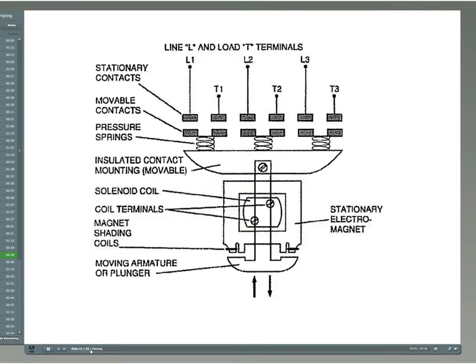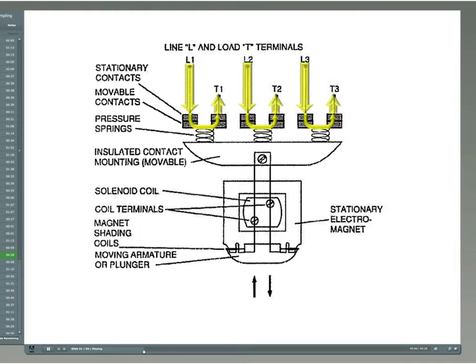Three-phase 480 volts AC is applied to L1, L2, and L3 when the breaker is closed. When coil voltage is applied to the electromagnet, the 480 volts AC is also being applied to T1, T2, and T3, and consequently to the leads of the motor. The motor will turn if the motor is good, and not being asked to work harder than its horsepower rating.